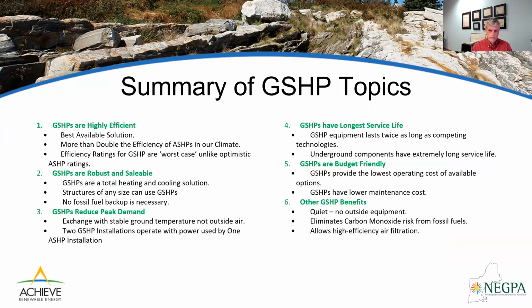Next slide. This is sort of a busy slide, but I'll try to hit the highlights, summarizing topics for ground source heat pumps. Not all of these topics will I be going into in detail today, but they could be the subject of future discussions. Ground source heat pumps are highly efficient — they have more than double the efficiency of air source heat pumps on an actual annual basis in our climate. That is sometimes hard to discern because the rating system used for ground source heat pumps focuses on worst case conditions, and air source heat pump ratings are somewhat more optimistic.